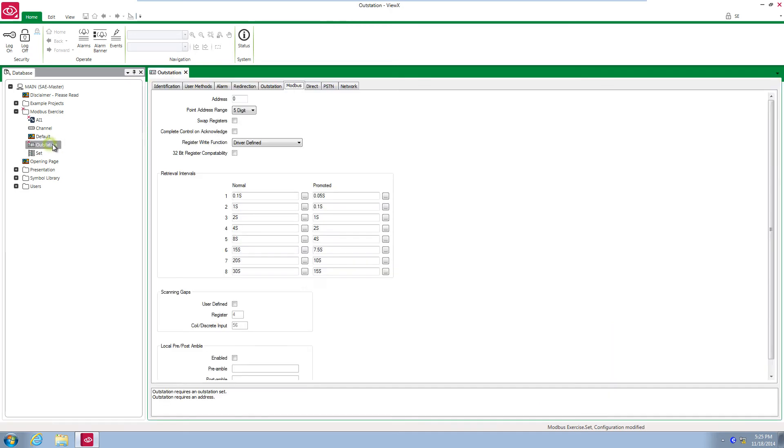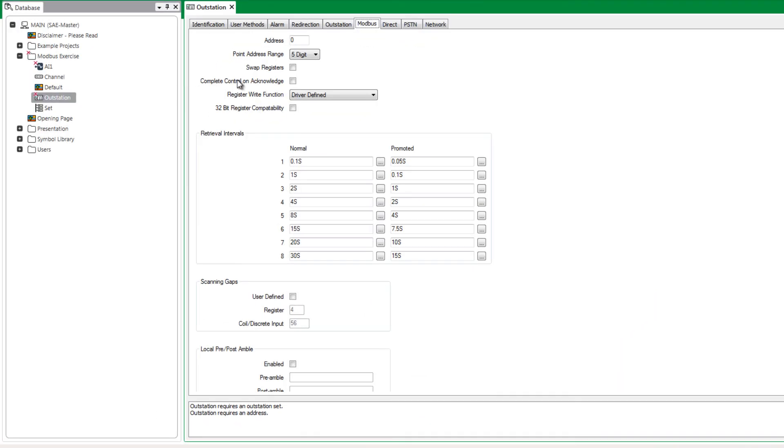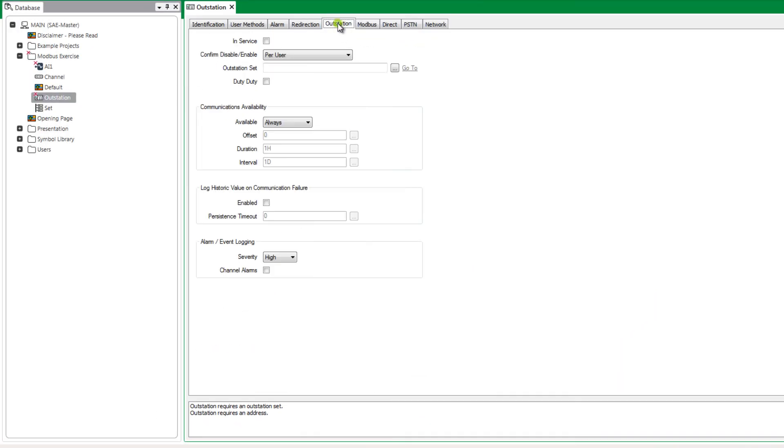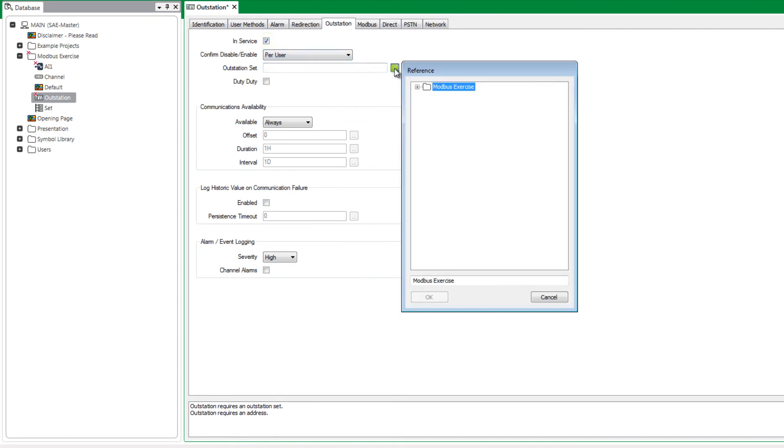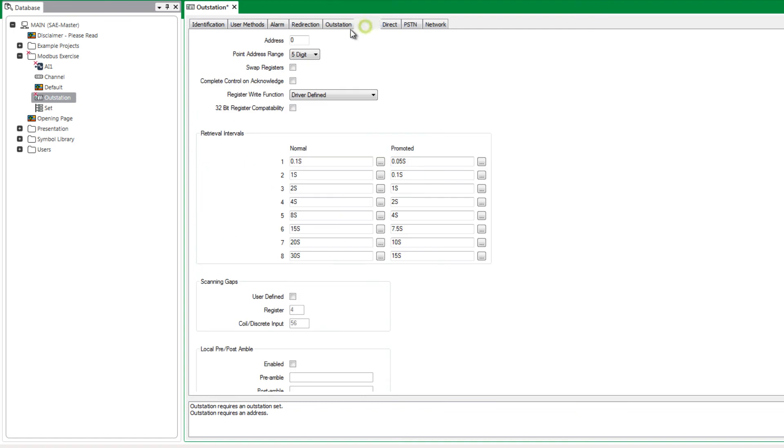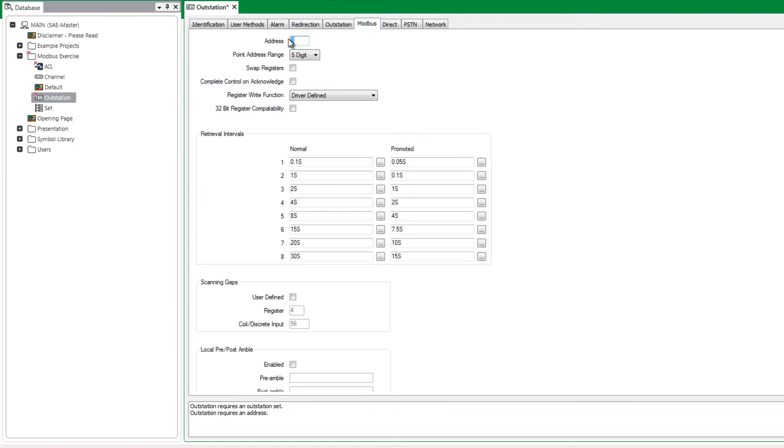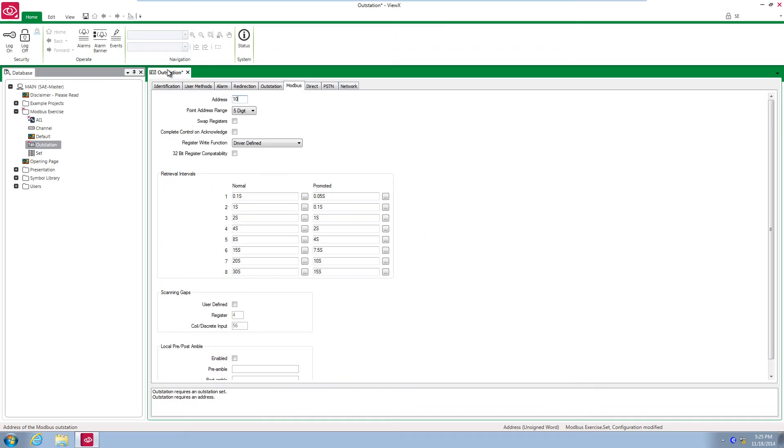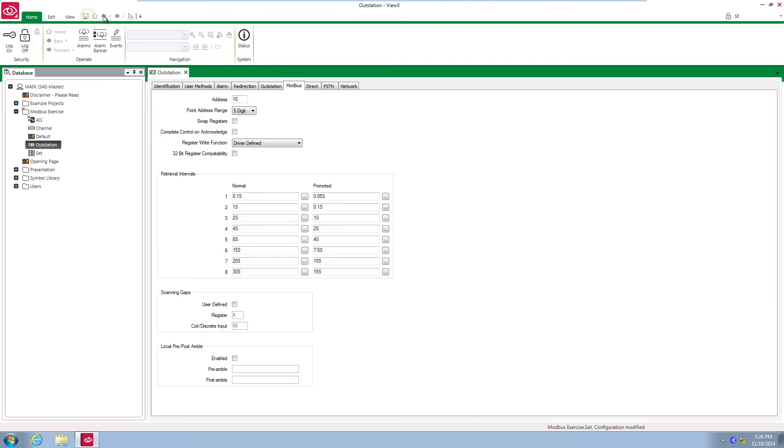Open the outstation object. Go to the outstation tab and put it in service. Hit the browse button next to the outstation set field and browse to the set object. Open the Modbus tab and set the address to 10. Save and close the object configuration form.